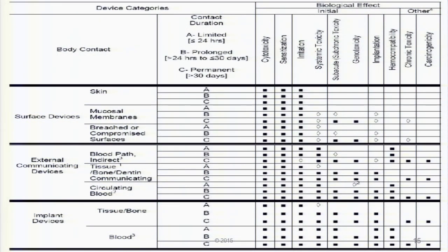Great question. And so what we give you is, so I'm going to go back real fast. So there are a couple answers to that question. One is if you see the diamonds here, these are tests the FDA may consider necessary. Honestly though, that's still up in the air because if your device is well categorized and well used materials, a lot of times the diamonds won't be asked for. But there are certain devices and certain contact uses that the FDA are concerned about. For example, we've seen a lot of personal lubricants asked to do a lot more testing than what the ISO says because the FDA is concerned about repeated use of a vaginal contact.